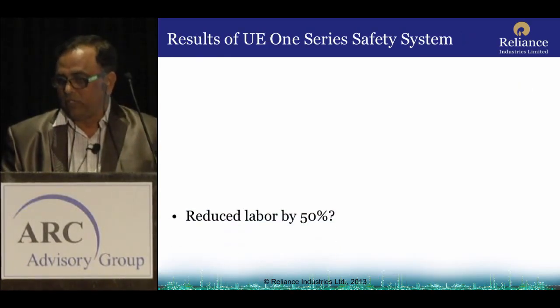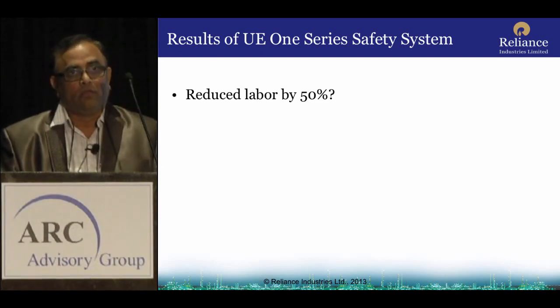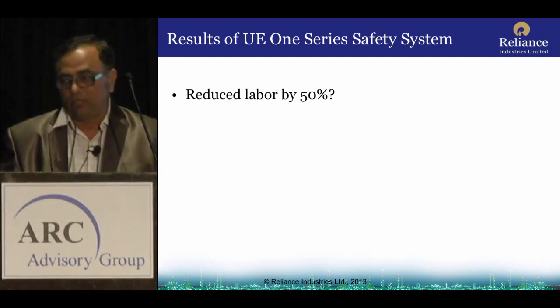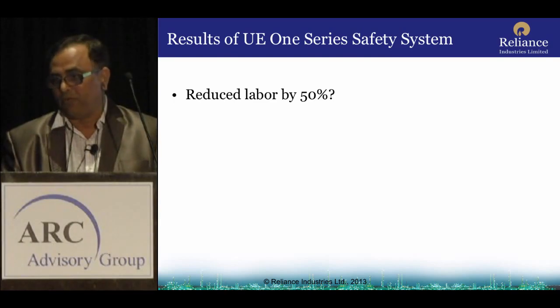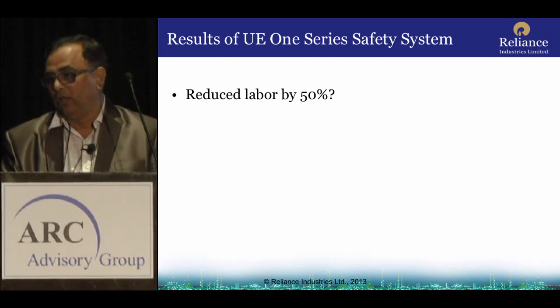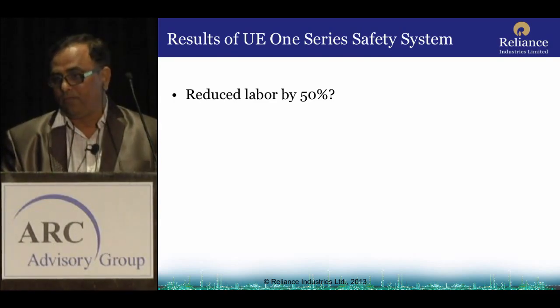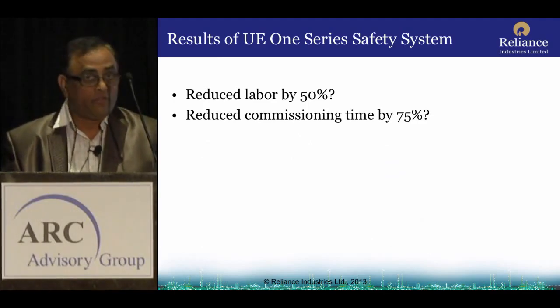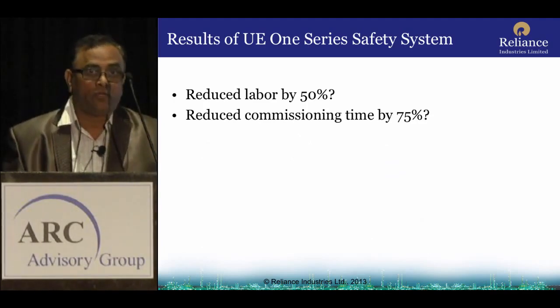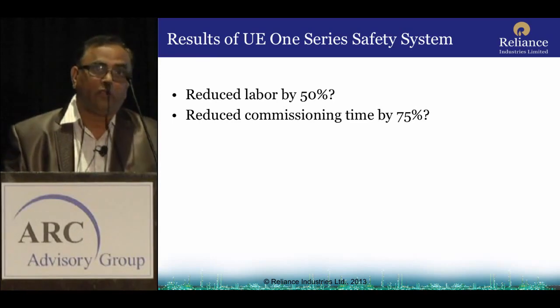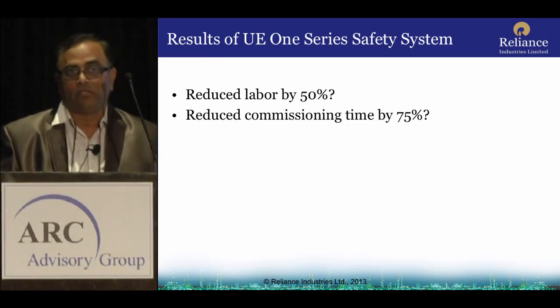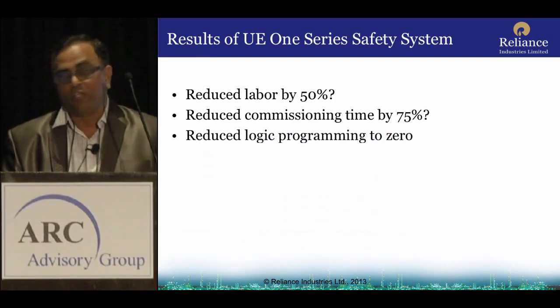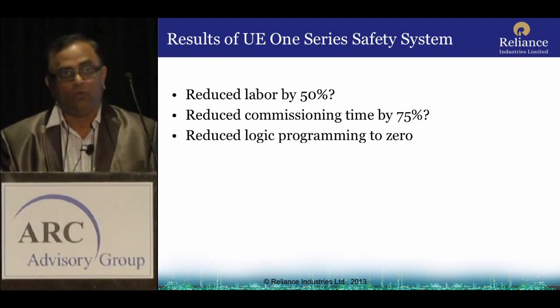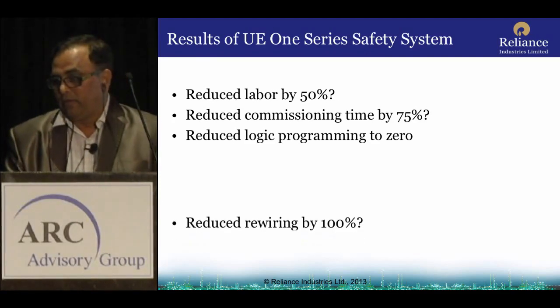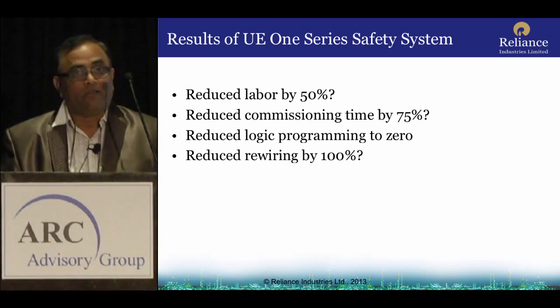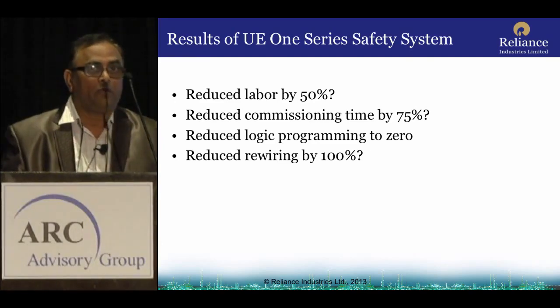So, what was the result? The replacement resulted in reduced labor by 50%, and reduced commissioning time by 75%. It was calculated based on the total micro activities involved in executing the system. Logic programming was reduced to zero, with no change in the logic. Rewiring was reduced by 100%, as the same cables are being terminated.